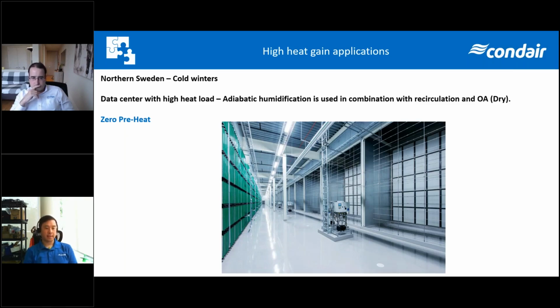The other picture that we're looking at here is actually the previous phase of the same facility where we supplied our atomizing high pressure systems, where we're actively spraying water into the airstream at about 1,000 PSI. One of the big differences here was the water quality requirement. Anytime we spray water or atomize water into the air, we have to make sure that we are pulling those minerals out, anything that is in that water, before we spray that into the airstream. Otherwise, those minerals will precipitate out as white dust. They'll clog filters. They could potentially damage sensitive equipment downstream.